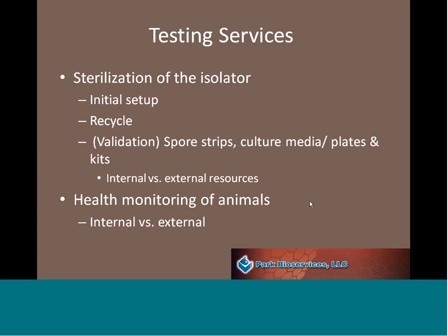So, testing services. Why I'm bringing up testing services is that, unlike a lot of things that are done in typical lab animal and SPF settings, it is very important to validate the equipment and also the supplies. So you have the initial sterilization of the isolator. Typically, one of the things that I recommend for that initial setup is to use Clidox. Another alternative is to use peracetic acid based sterilants first, something like Spore Cleanse.